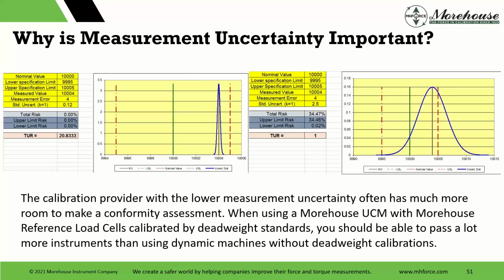If you use a calibration provider with lower measurement uncertainty, you often have a lot more room to make that assessment. But if I make that assessment on the left and I give that to a customer and then they use that as the reference, unless they load that device consistently to 10,004 pounds or 10,004 newtons, whatever it is, to generate 10,000, when they want to apply 10,000, there's an additional error. And I do not think people are doing this. So the best thing to do is use coefficients to correct it. Other than that, if we assign values and say, hey, at 10,000, it read 10,004, you want to apply 10,000, you need to load it to 10,004.